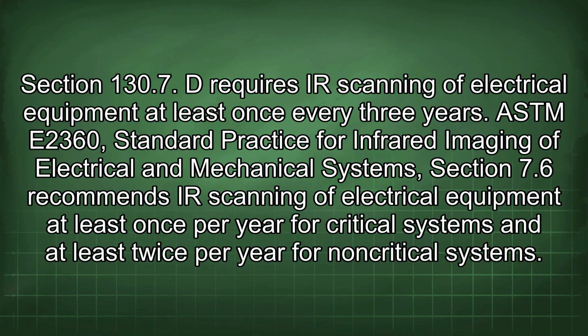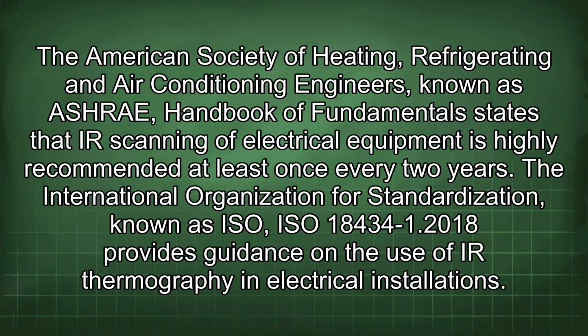ASTM E2360, Standard Practice for Infrared Imaging of Electrical and Mechanical Systems, Section 7.6 recommends IR scanning of electrical equipment at least once per year for critical systems and at least twice per year for non-critical systems. The American Society of Heating, Refrigerating and Air Conditioning Engineers, known as ASHRAE Handbook of Fundamentals, states that IR scanning of electrical equipment is highly recommended at least once every 2 years.